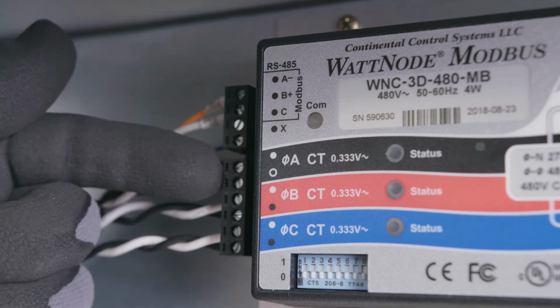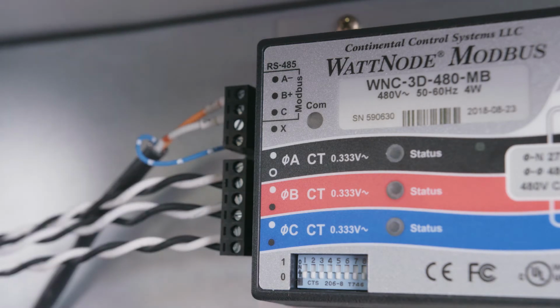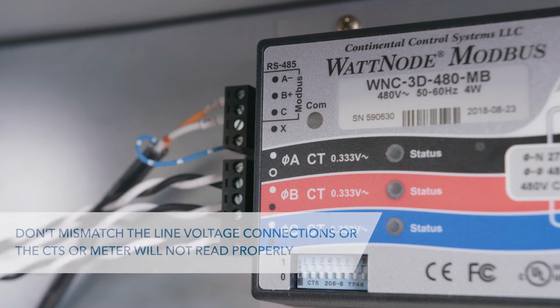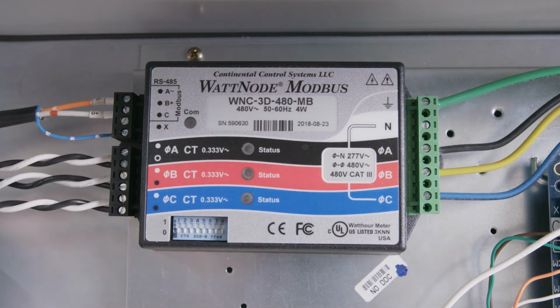On the left-hand side, you have terminals for A, B, and C phases, which need to be connected to the CTs. Please note that the line voltage connected to line A must have the CT connected to that same line voltage. You can't mismatch the line voltage connections and the CTs, or the meter will not read properly. The phases have to be correlated to A phase, B phase, and C phase. Also make sure that when you terminate the wires, you have white on top of black for each set of CTs, and so on. White on top, black on bottom, white on top, black on bottom.